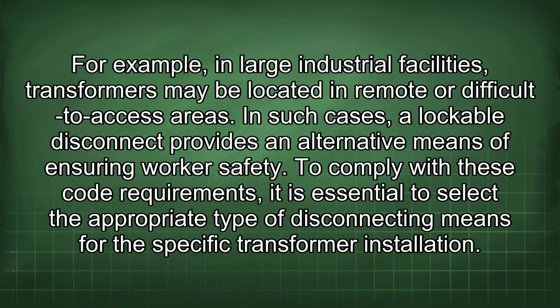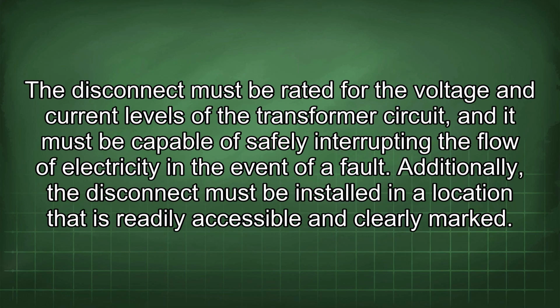For example, in large industrial facilities, transformers may be located in remote or difficult to access areas. In such cases, a lockable disconnect provides an alternative means of ensuring worker safety. To comply with these code requirements, it is essential to select the appropriate type of disconnecting means for the specific transformer installation. The disconnect must be rated for the voltage and current levels of the transformer circuit, and it must be capable of safely interrupting the flow of electricity in the event of a fault.